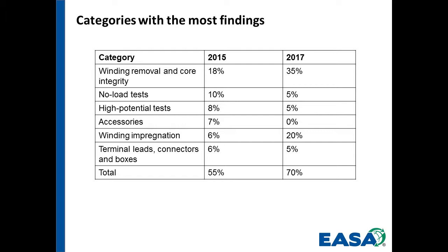Now, this is a little misleading. It's not that there were that many more. In 2017, the number of findings was less overall than we found in 2015. So it's a bigger piece of a smaller pie, which is a positive thing. But the point is that with winding removal and core integrity, if you want to know the number one thing to be looking at in your program, go through that category and make sure that you really are in conformance there, because that's probably your number one weakness area.